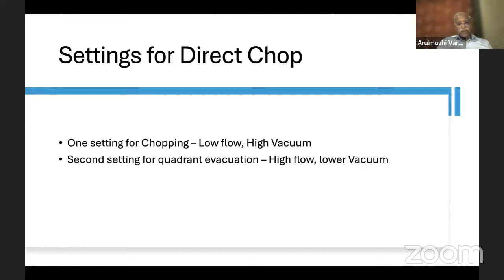I like to keep a standard flow rate across all the procedures. So my flow rate is either 50 to 60 and a vacuum of 500 or 600. You have to understand what does flow rate do and what does vacuum do. Flow rate will pull pieces towards you once they are disassembled. Anything that is not disassembled is not going to be pulled out, even if the flow rate is high. Vacuum is going to hold. After vacuum is built up, it is going to hold very well. So the hold is very important when you want to do a chop.